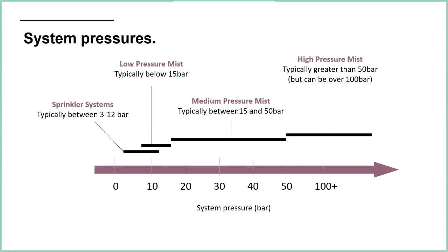Low pressure mist is typically below 15 bar. You can see there's some overlap between a low pressure mist system and a medium to high pressure sprinkler system, which operate on a similar pattern. Medium pressure mist is between 15 and 50 bar, and high pressure mist is anything over 50 bar, but can go over 100 bar in terms of operating pressure.